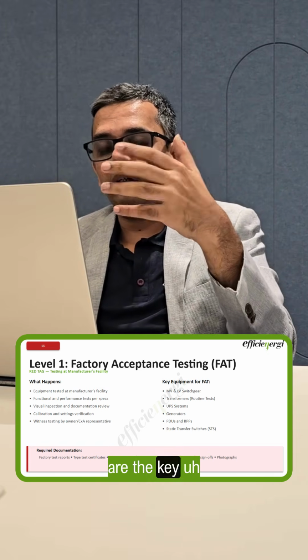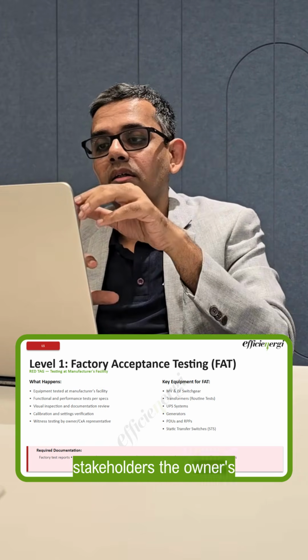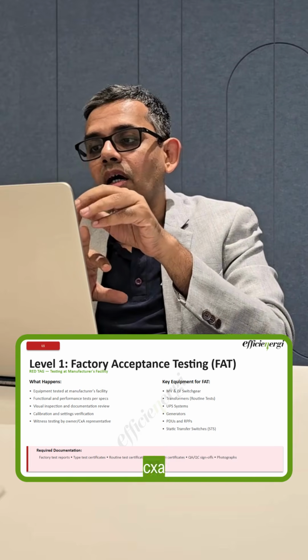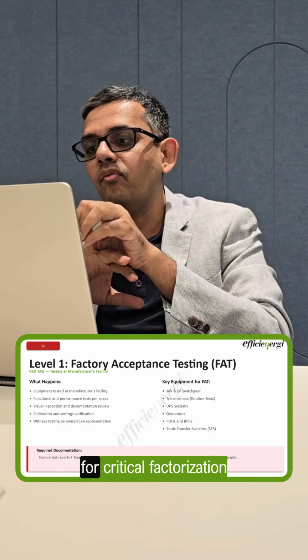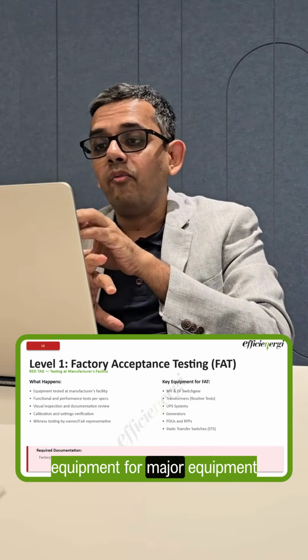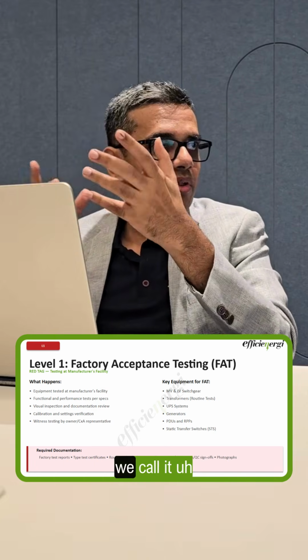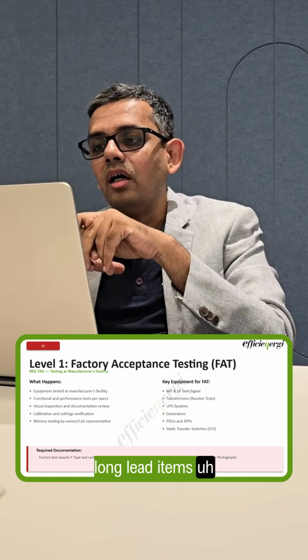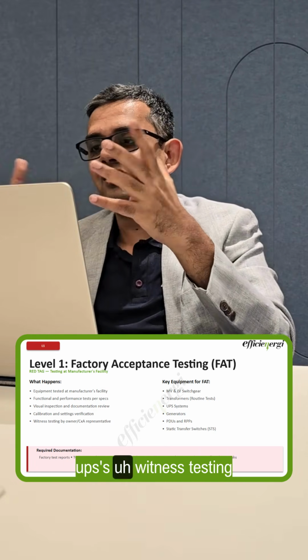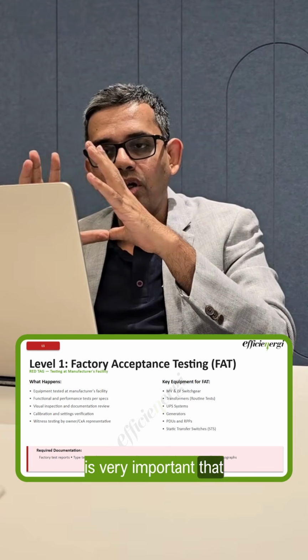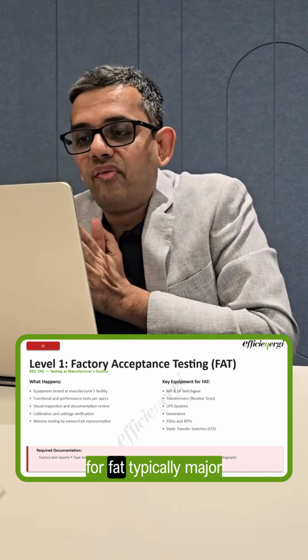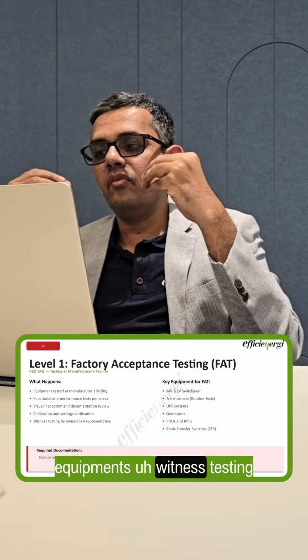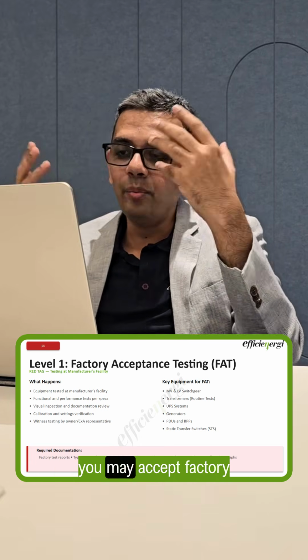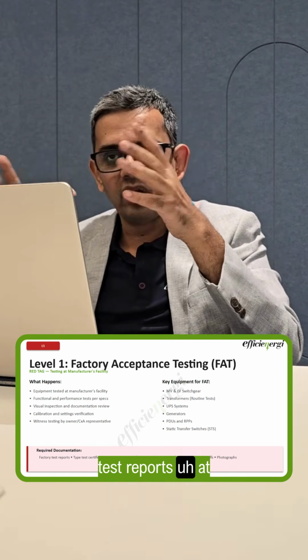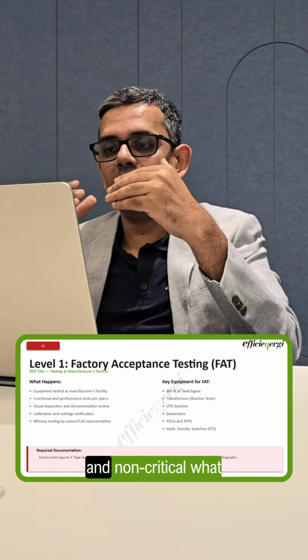That is most important. It's much easier and cheaper to fix issues at the factory than at the site. Who typically attends this? The key stakeholders: the owner's representative is there, and CxA witnesses attend for critical FAT items. For major equipment, long lead items like switchgear, transformers, and UPSs, witness testing is standard and necessary. For smaller, non-critical equipment, you may accept factory test reports instead.